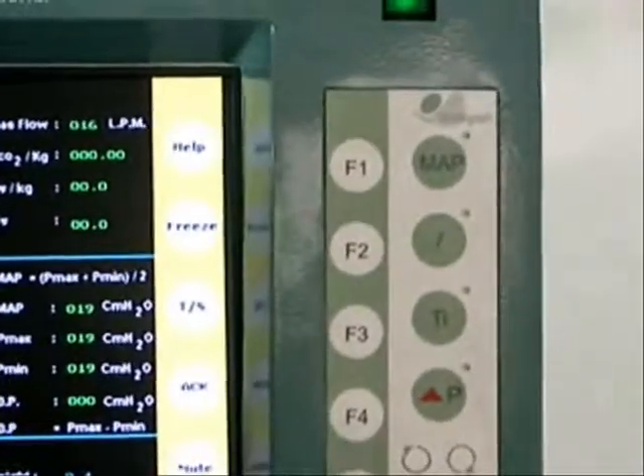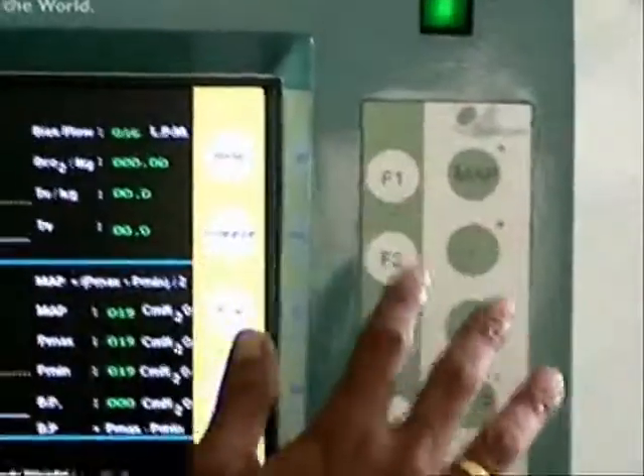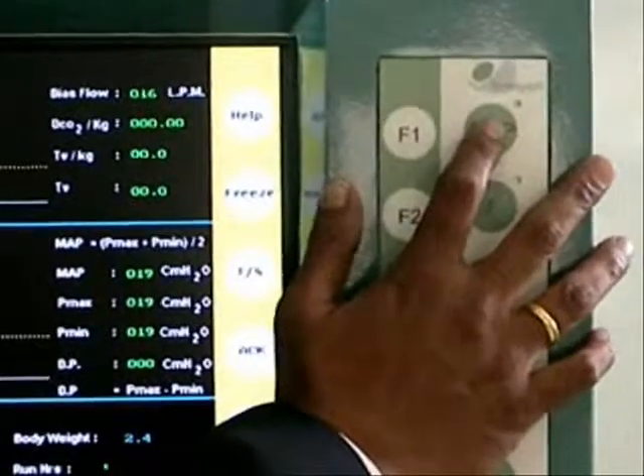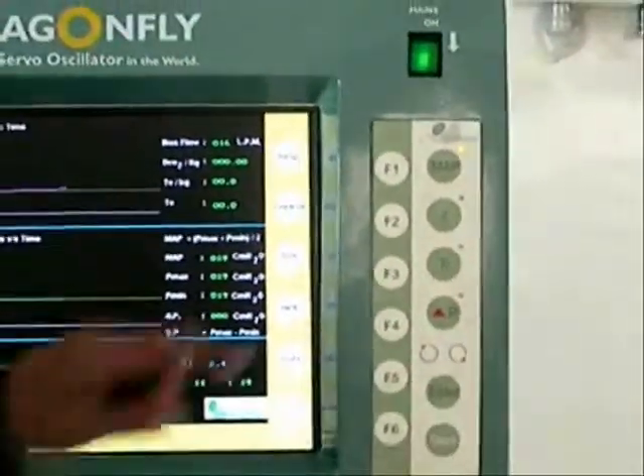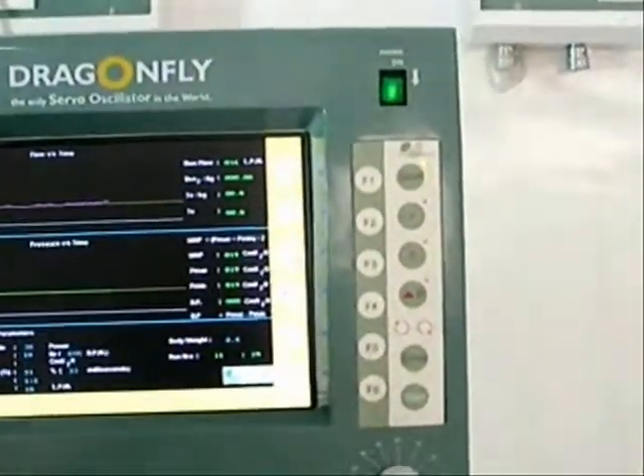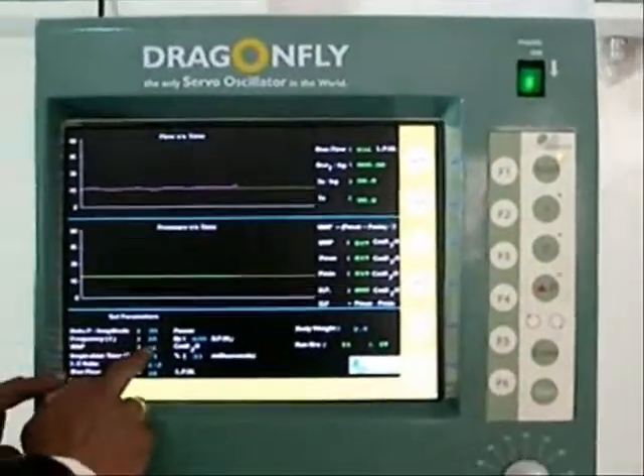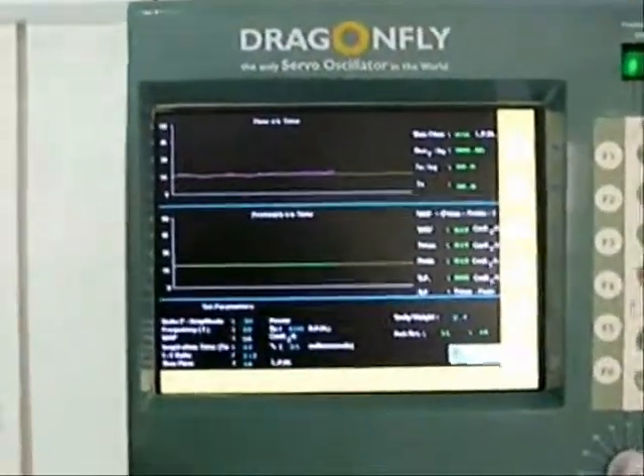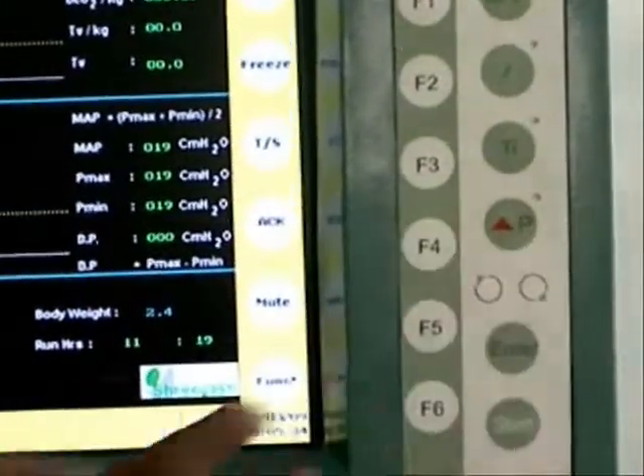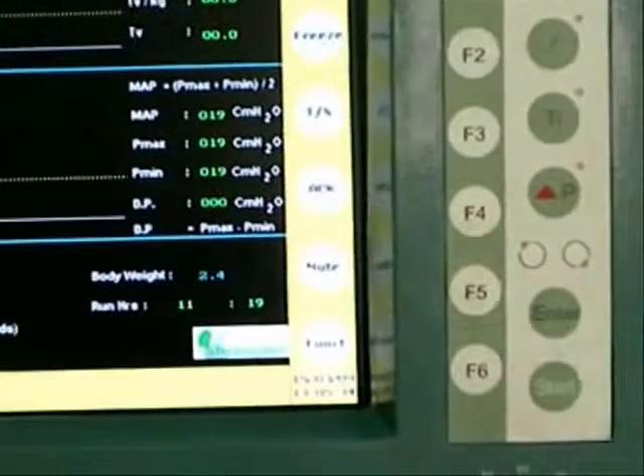For example, now I want to set a mean airway pressure of say 16 or 15 centimeters. So I just press this mean airway pressure. Now this light has glowed. Simultaneously, the MAP display here is flickering, so one can know what parameter you are setting. Now using these up and down keys, you can adjust the mean airway pressure. Once you adjust it, just press enter.